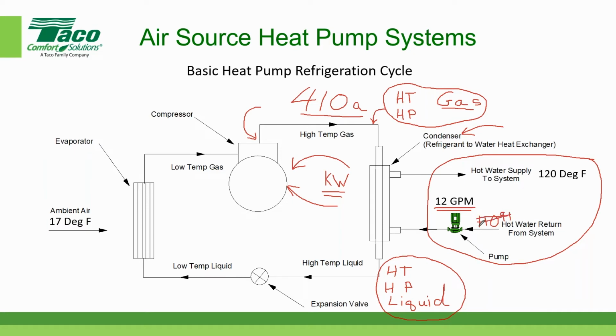oops, that's supposed to be Fahrenheit, Brett, and it came out looking like a goofy thing here. Let me cross that out. I'll do this one more time. That was tough to follow. So the water's entering at 110 degrees, with a degree symbol, Fahrenheit, F. That's better. So we're going to pump the water. Now, generally, by the way, especially for colder climates, it's usually a water glycol solution. For tonight's example, it will be a water glycol solution, but I've just labeled it water here. So the water enters the plate and frame heat exchanger at 110 degrees. It extracts the energy from the refrigerant, causing the refrigerant to condense into a liquid from a gas at the same temperature and pressure, and then leaves at 120 degrees Fahrenheit.